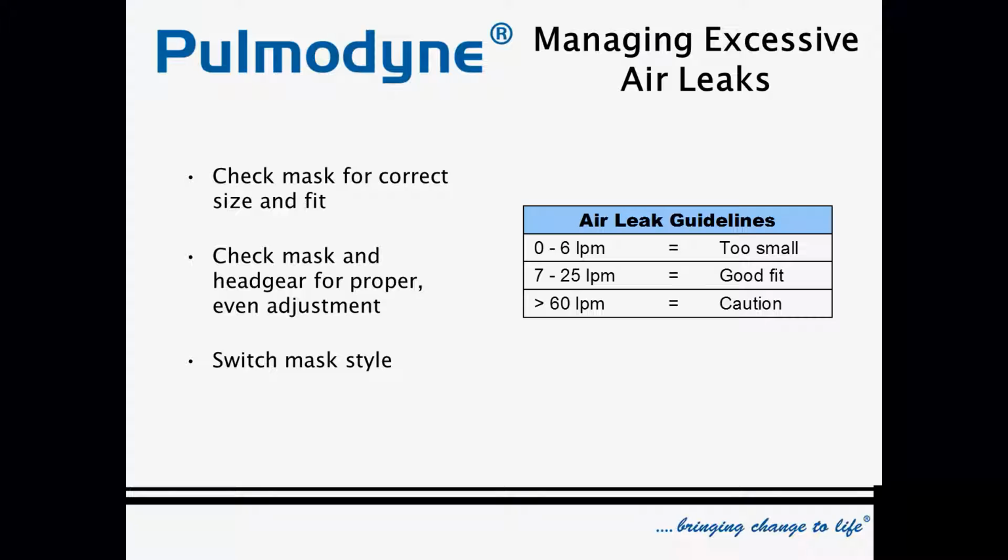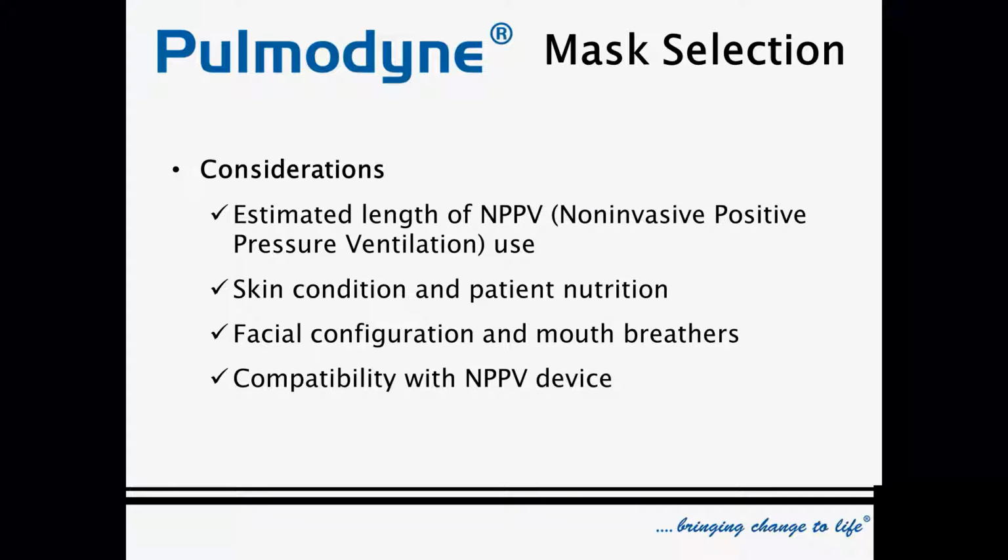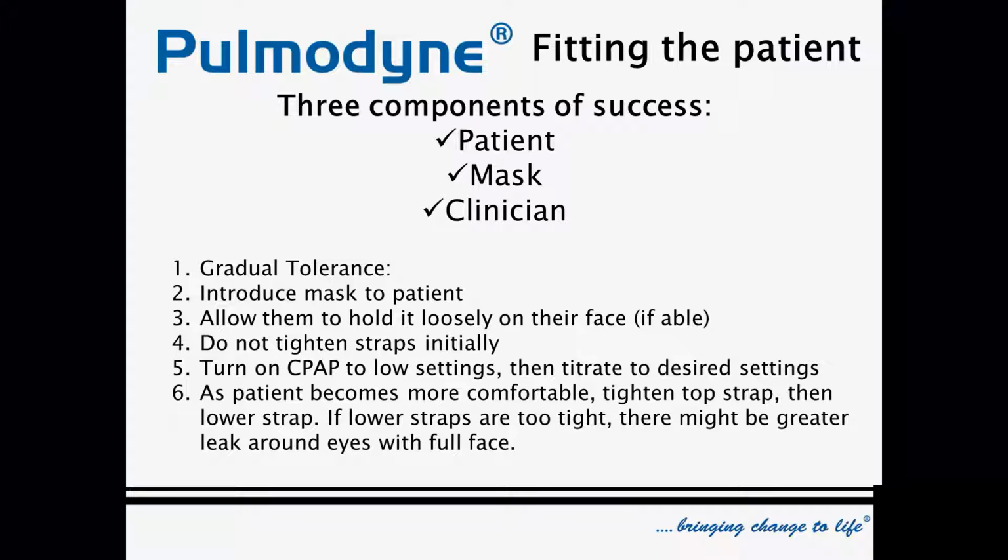As far as adjustments on the mask to fit in the parameters of the leak, Kevin mentioned we have a dual lip style cushion. One thing that is really unique about our product, that Philips has too, but all other manufacturers don't, is that if you want to reduce leak rates, you actually loosen the mask so that it doesn't disrupt the bubble seal. So that's the one thing I want to say there, Kevin. Okay, great.